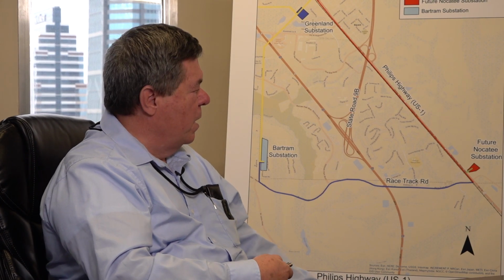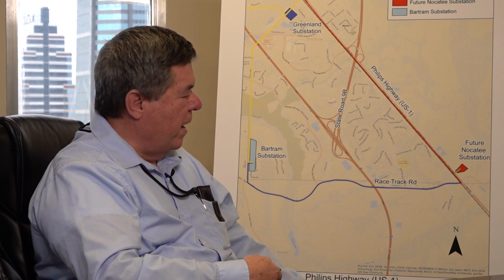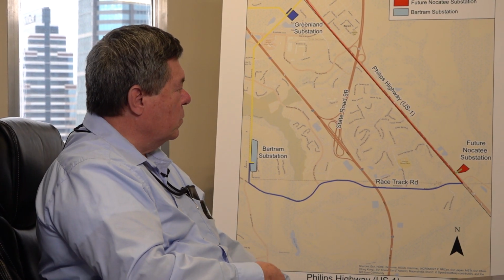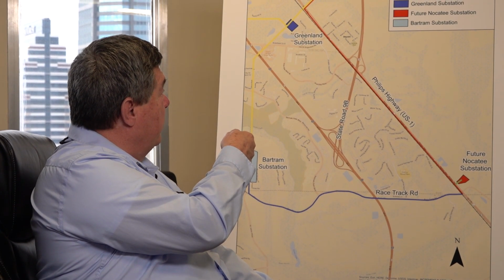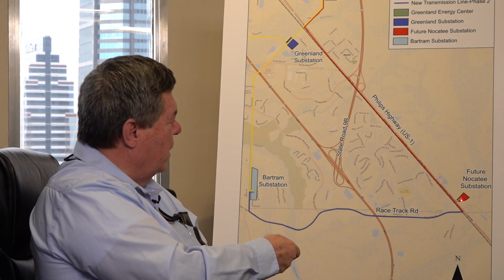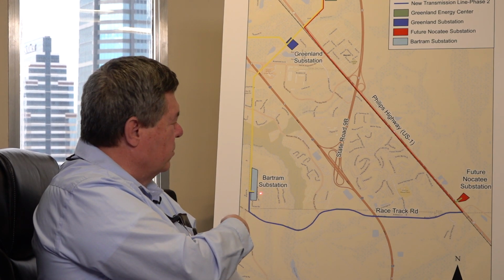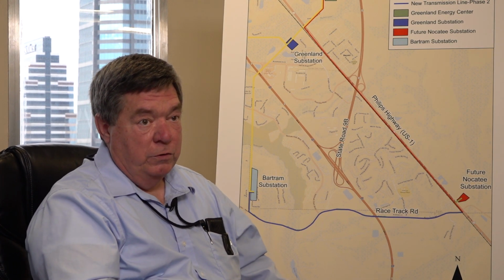So that substation hasn't been built yet? Correct, it hasn't been built. Now every substation has to have a source, it has to have power. So we'll energize this at 230 kV, and the source will be Greenland Energy Center. We come down here and go back around to the Bartram substation - two sources, one for each side. We build all of our substations that way, so in the event something happens to one of the sources, the other will continue to serve the load. It's an N-1 in planning lingo.